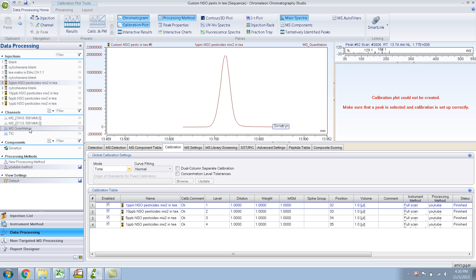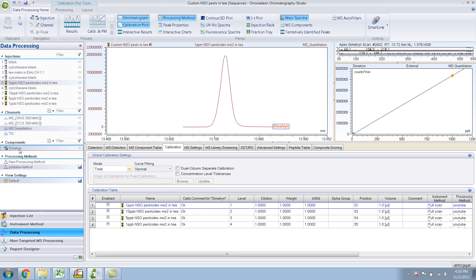The reason why it's not showing up is because we have these various channels which have been selected. Like I said, all quantitation and calibration, it's always done on the MS Quantitation channel for GCMS, for mass spec. So as soon as I click on mass spec, I get components. And as soon as I click on components, you should see your calibration plot for that component.